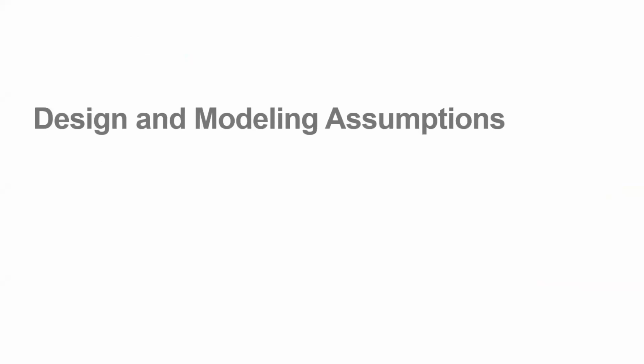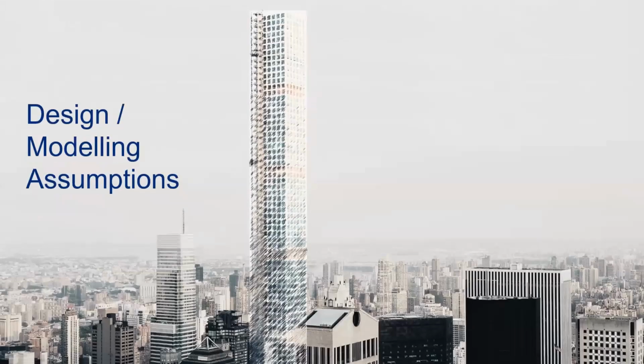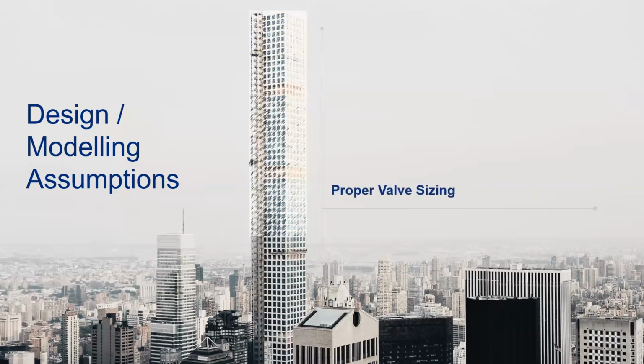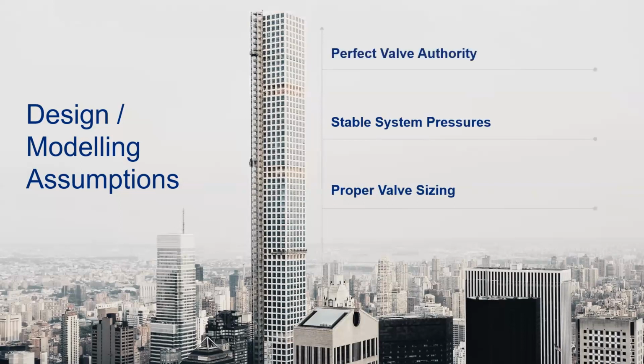We're going to jump right into design and modeling assumptions. Energy modeling software is limited in its capacity to model a truly dynamic system. As a result, there are three assumptions made regarding control valves that are not accurate in most hydronic installations today. We're going to go through those. The first one is proper valve sizing. The second one is stable system pressures. And the third one is perfect valve authority.